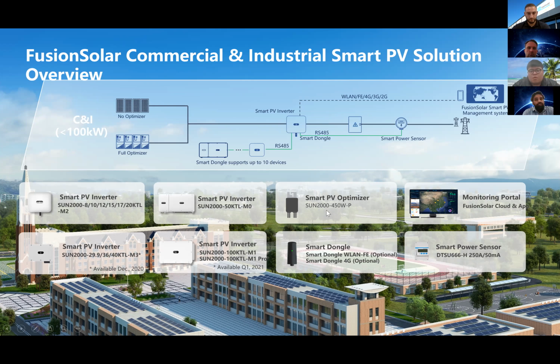Optimizers at this stage are the same 450-watt optimizers used in the residential scenario. Those optimizers are compatible with these inverters as well. Which inverters? M2s, 8 to 20 M2, 29.9, 36, 40 M3. So by next year, all inverters up to 40 kilowatt will be compatible with optimizers, and that is as an option.